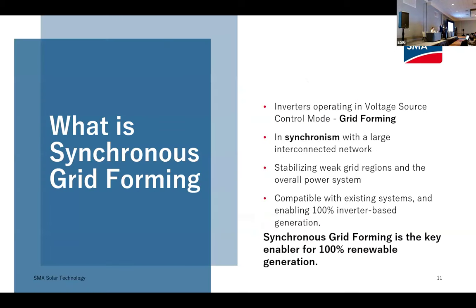Synchronous grid forming: building upon those controls, at SMA we talk about synchronous grid forming, which means we're operating synchronously or in synchronism with a larger network. We detect the voltage and frequency at the very beginning of turning on the inverter, and then we're operating in synchronism with the network from that point forward. These are always voltage source converters when talking about grid forming, compatible with existing networks, and that control mode acts to bring about stability and strengthening of the grid. We see this as very fundamental and key to enabling very high penetrations of renewables, if not 100%.